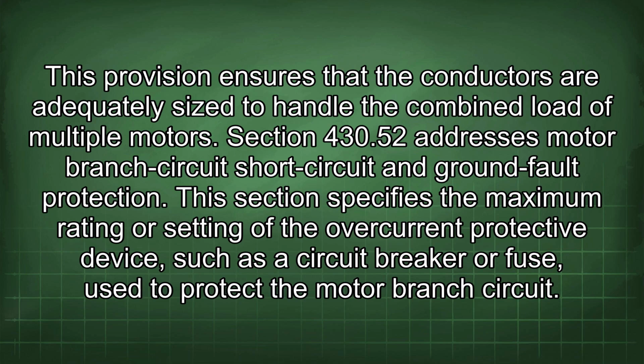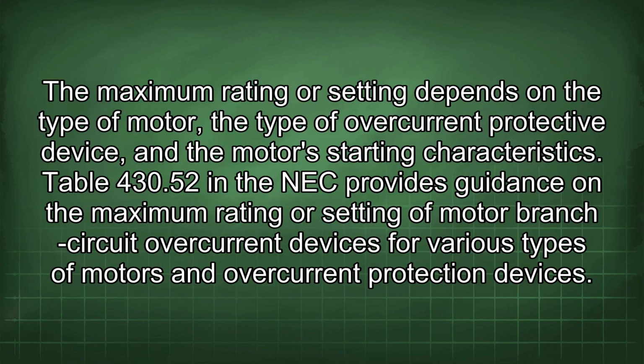Section 430.52 addresses motor branch circuit, short circuit, and ground fault protection. This section specifies the maximum rating or setting of the overcurrent protective device, such as a circuit breaker or fuse, used to protect the motor branch circuits. The maximum rating or setting depends on the type of motor, the type of overcurrent protective device, and the motor's starting characteristics. Table 430.52 in the NEC provides guidance on the maximum rating or setting of motor branch circuit overcurrent devices for various types of motors and overcurrent protection devices.